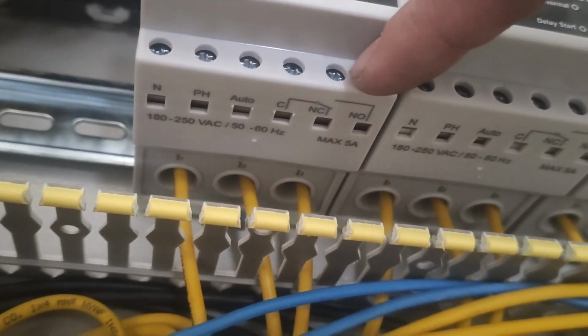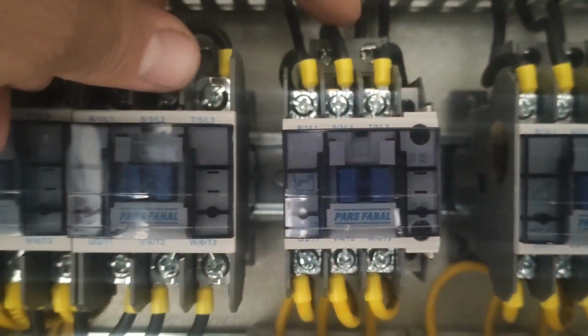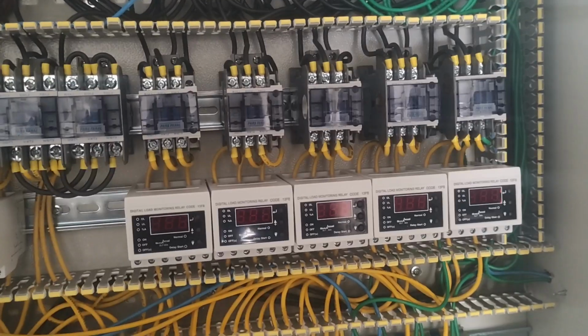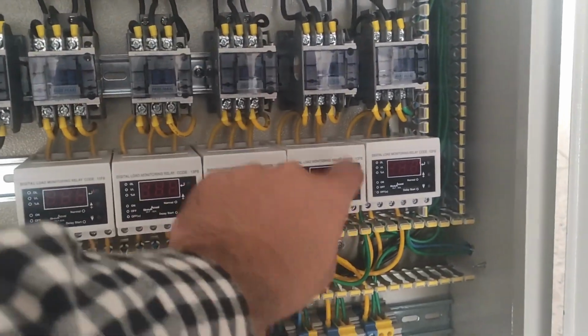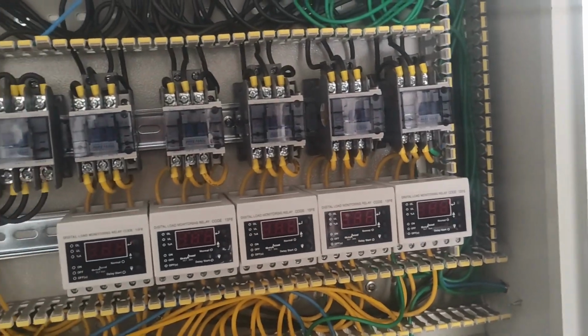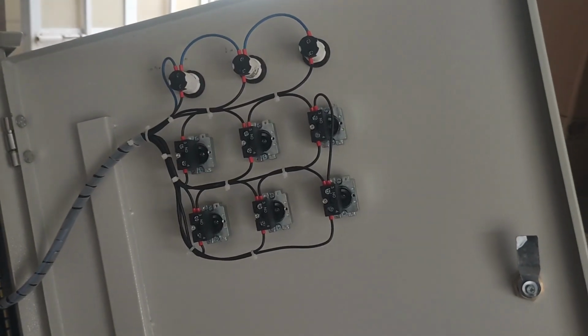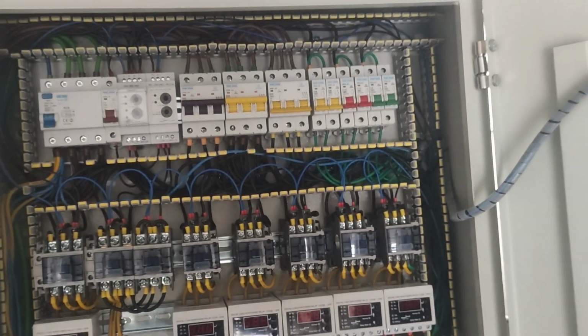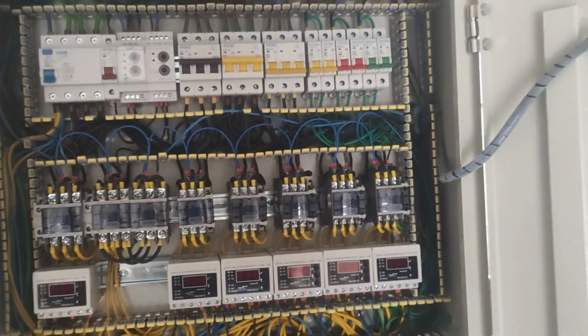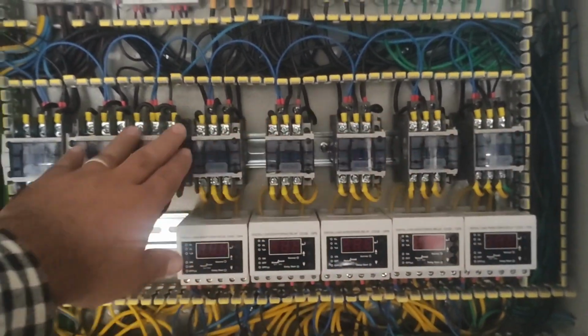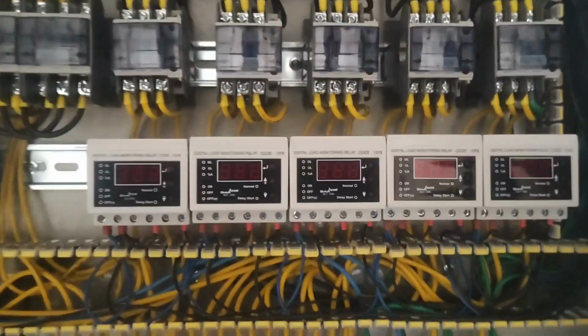Also, the output of each of them is connected to the input of the current controller relay, which are labeled with PH and C. And the output of these relays is connected to the coil of the corresponding contactors. In this part, we wired the entire control circuit and connected all the current controller and phase controller relays and contactors that needed a neutral wire to the neutral wire.